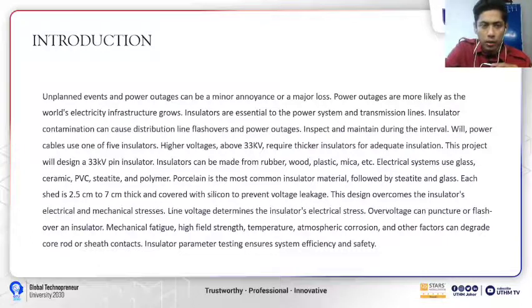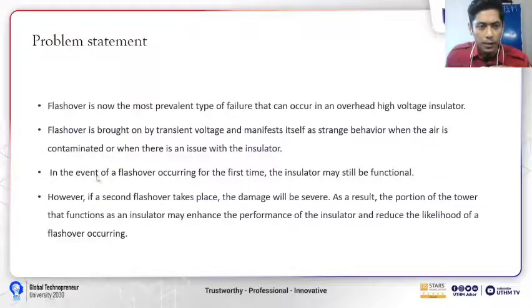So I go through the problem statement. First, flashover is now the most prevalent type of failure that can occur in an overhead high voltage insulator. Flashover is brought on by transient voltage and manifests itself as strange behavior when the air is contaminated or when there is an issue with the insulator. In the event of the flashover occurring for the first time, the insulator may still function, but when the second flashover takes place, the damage will be severe. As a result, the portion of the tower that functions as an insulator may enhance the performance of the insulator.